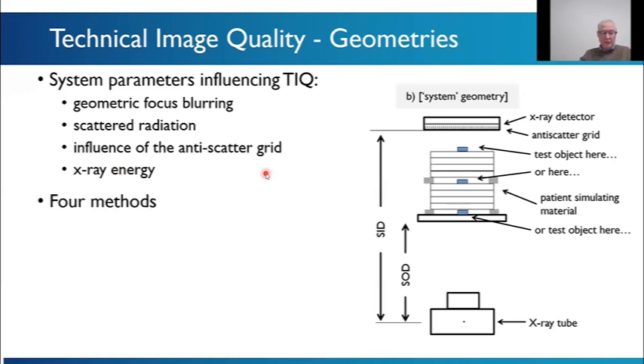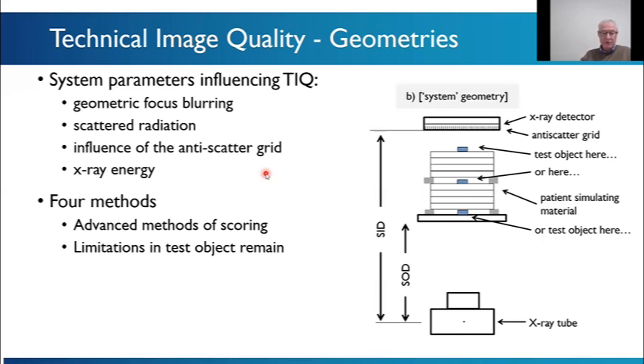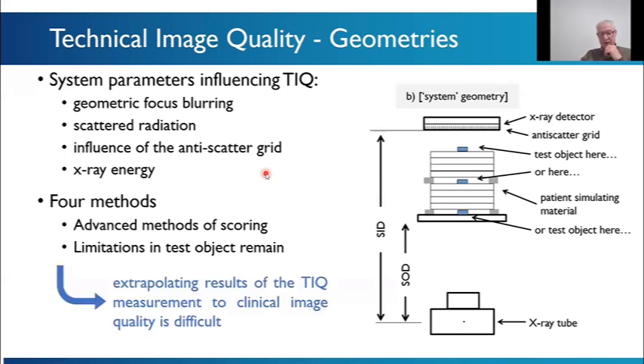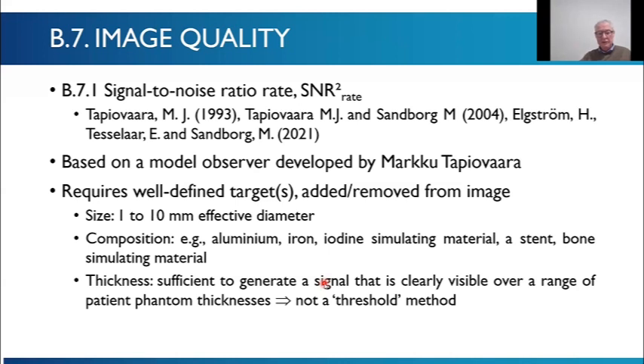Well, it does. And we've specified 4 methods. They're kind of contrast detail based or low contrast resolution of the detector. And there are some limitations of the test objects, which I'll discuss briefly at the end. But we're extrapolating results from the technical image quality test to a clinical image quality. And that is quite difficult to do. As Annalisa said, the technical tests and the test objects are quite limited and don't fully simulate patients to any degree, really. So there are three main calculated methods. So we want to go from a visual image scoring method, which is subjective and has problems comparing against standards and comparing against other colleagues, for example, because you have to count how many discs you would normally see, to a calculated method where you have access to the image data and you calculate your result.